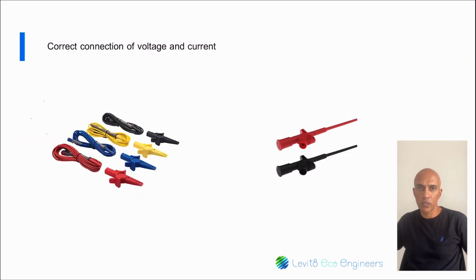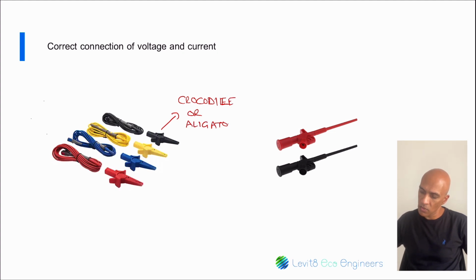Now, here we have photos of typical type of voltage clips. So depending on where you are able to connect your voltage leads to, there are various types of clips that can be used. The standard crocodile or alligator clips are useful for connecting to bus bars, and in some cases to circuit breaker terminal bolts on large circuit breakers. So these crocodile or alligator clips, it depends where in the world you come from. In South Africa we call them crocodile, and in USA you would probably call them alligator. So you would connect these, and then they've got their leads, and these leads go directly into the instrument.